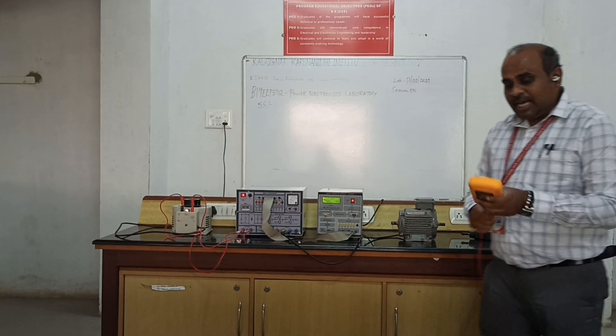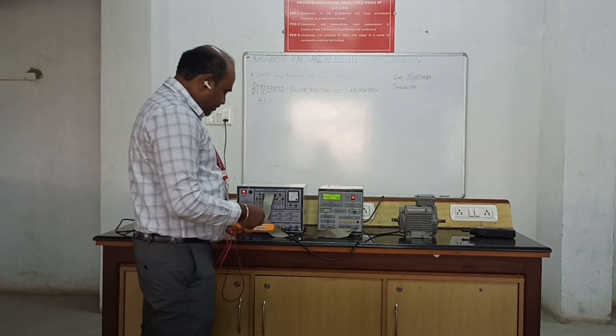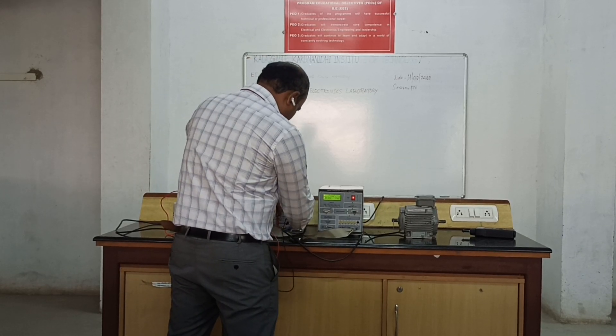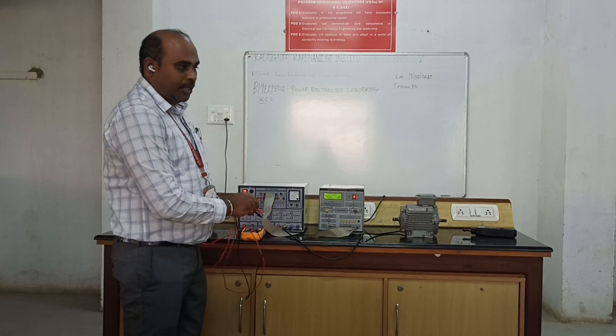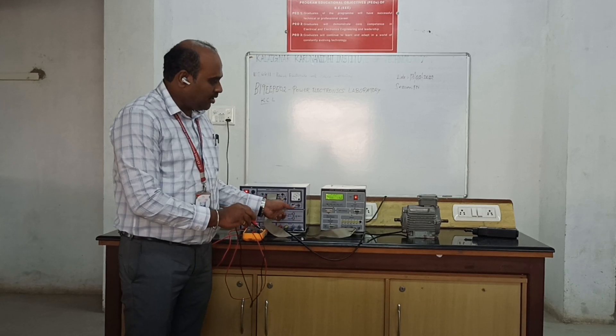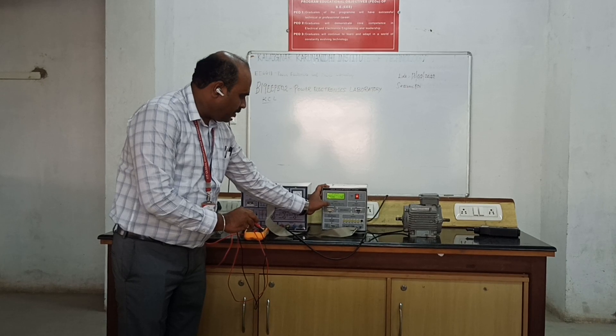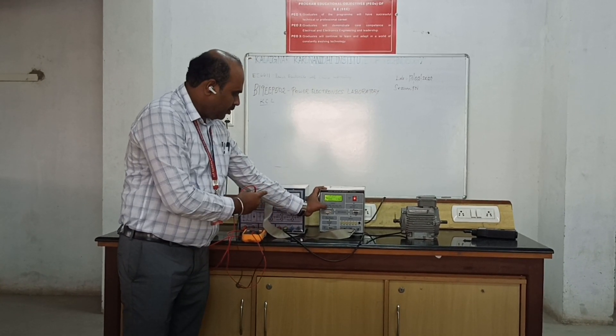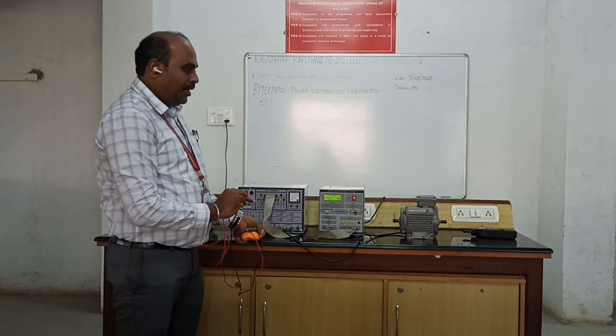We check the output voltage on the multimeter in AC mode. The output voltage now reads 34 volts. We slowly increase the frequency to 30 Hz and observe the motor speed also changes, rising to around 850 RPM. The output voltage also rises to 48 volts.